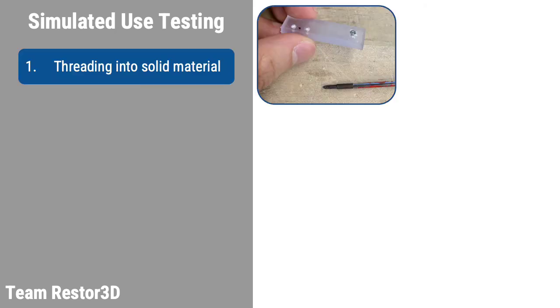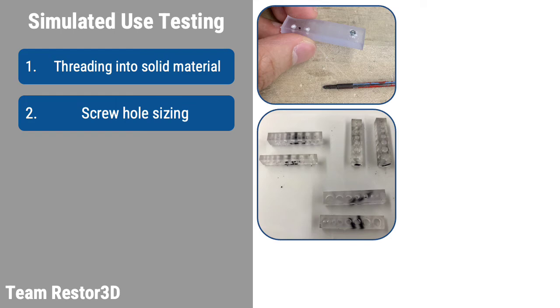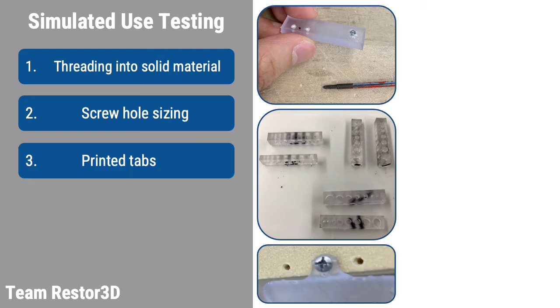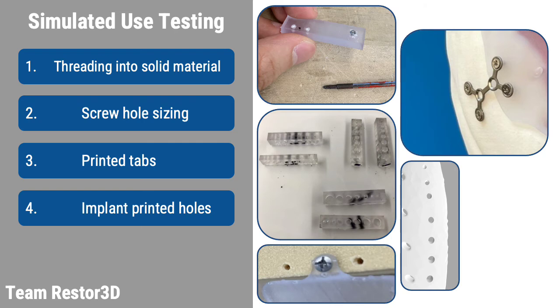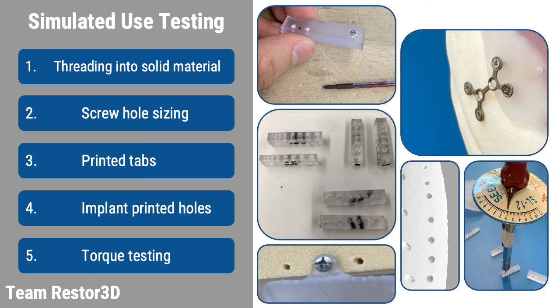One part of our testing process is testing the simulated use of our device based off the requirements we defined. We tested screwing into plain material, testing how hole sizes changed when the implant was printed, if printed tabs are feasible, how to screw into holes when they're on the implant, and how much torque it takes to screw into various hole sizes. This testing had a mix of qualitative and quantitative results, and it was an important step in guiding our design choices.